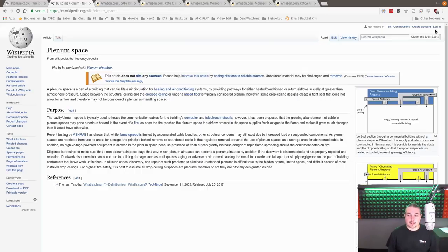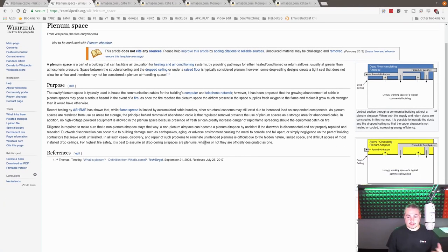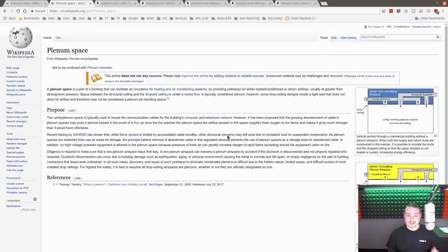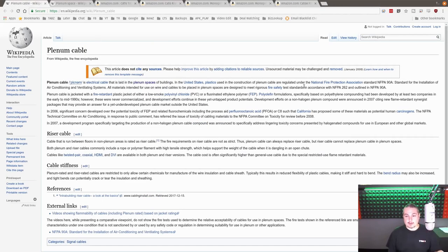And one of the other comments I had in my previous video when someone said, well, it's not a municipal thing. Well, actually for us, it has been. We have some cities that require it, because they have inspections on this, it's a city thing. They require plenum. They don't care if it's going in a wall or not. They just have a rule. So that being said, plenum, if you're sharing an airspace, may be a requirement based on some municipalities. And it is recommended if you're a National Fire Protection Association, they have specific rules. And I'll leave a link to this Wikipedia article.